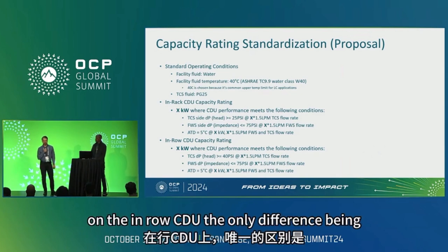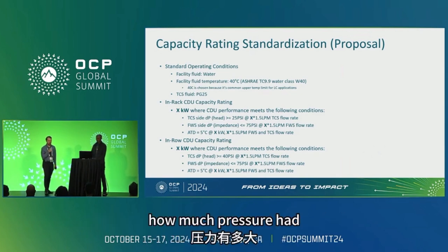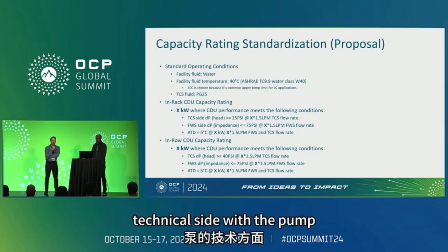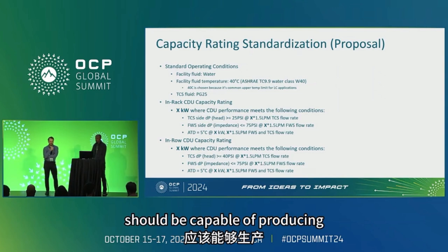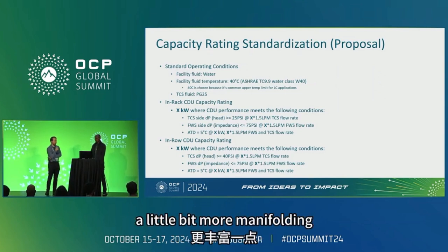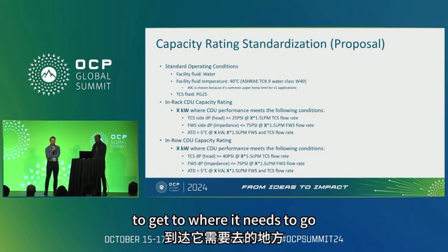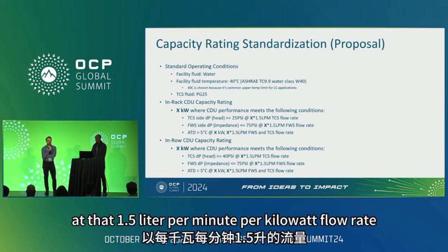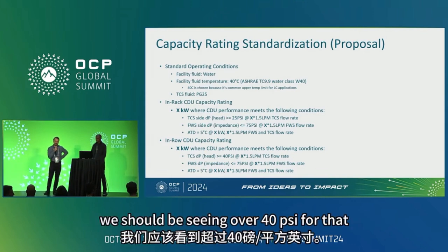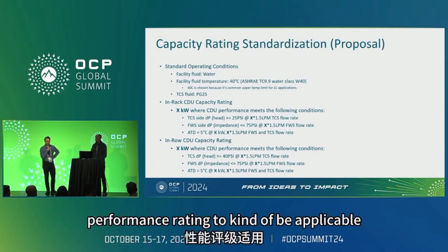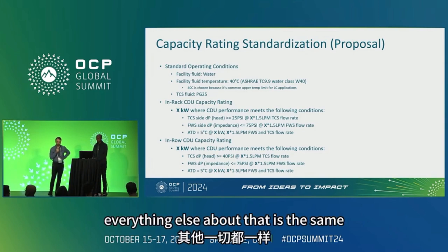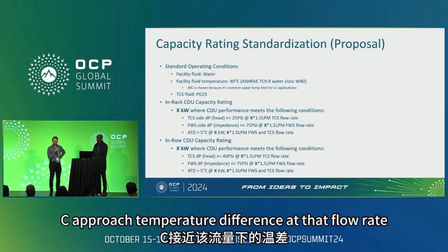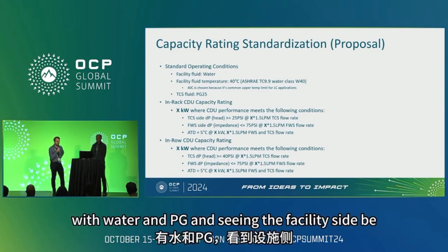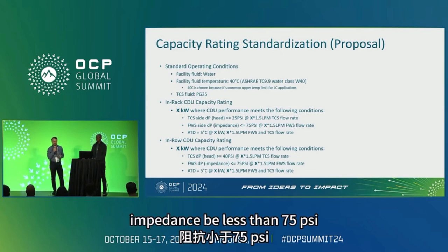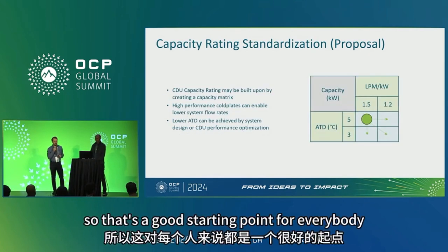Very similarly, on the in-row CDU, the only difference being how much pressure head the technical side with the pump should be capable of producing, because it has to flow through a little bit more manifolding, maybe a few more connections to get to where it needs to go. So we're proposing that at that 1.5 liter per minute per kilowatt flow rate, we should be seeing over 40 psi for that performance rating to kind of be applicable. Everything else about that is the same, where we're looking at the 5 degrees C approach temperature difference at that flow rate with water and PG, and seeing the facility side impedance be less than 75 psi. So that's a good starting point for everybody.